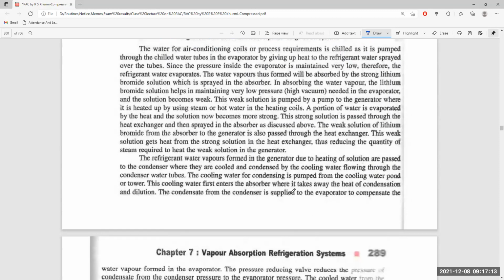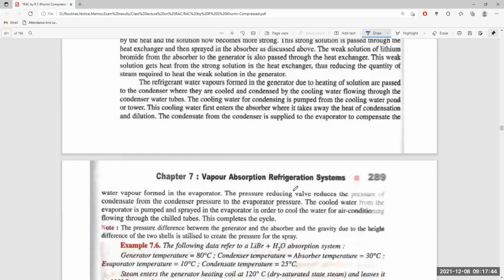Now, the refrigerant water vapor, due to heating of solution, is passed to the condenser where it is cooled and condensed by the cooling water flowing through the condenser water tube. The cooling water for condensing is pumped from the cooling water pond or tower. This cooling water enters the absorber where it takes away the heat of condensation and dilution. The condensate from the condenser is then supplied to the evaporator to compensate the water vapor formed in the evaporator.